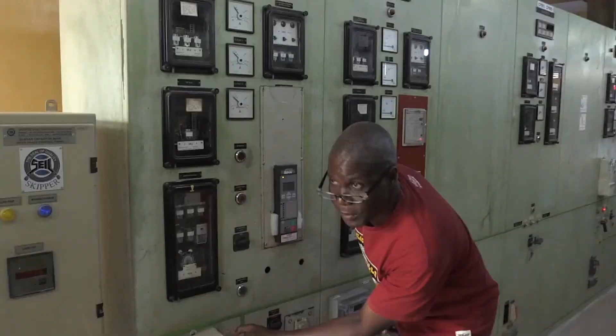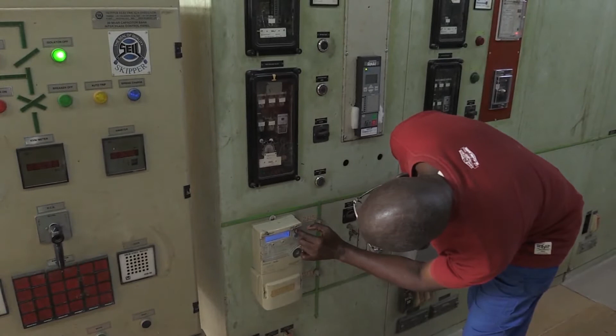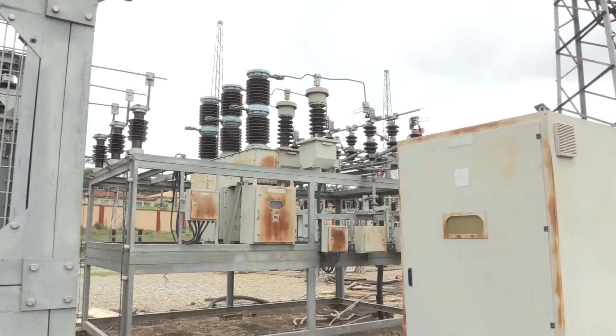The preventive maintenance is done annually on our transformers to find out their performance and detect any abnormalities. Through the comprehensive tests carried out during preventive maintenance, we are able to detect if the transformer is having an issue or not. We do that on the transformer as well as the switchgear equipment. For most of the switchgear equipment, we also have what we call quarterly maintenance to find out whether the circuit breakers, isolators, and other components are having issues.